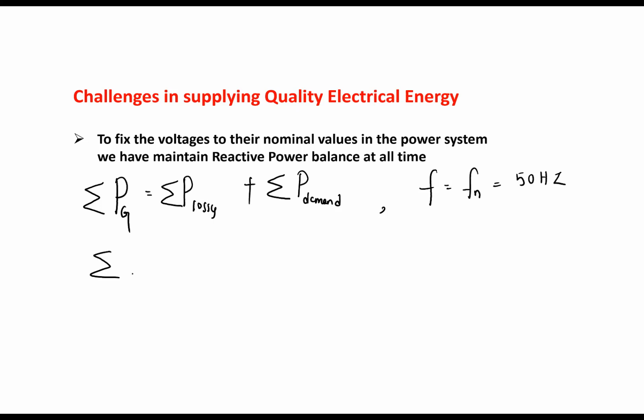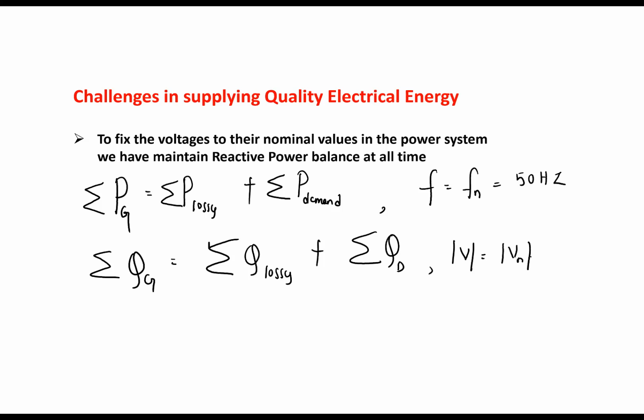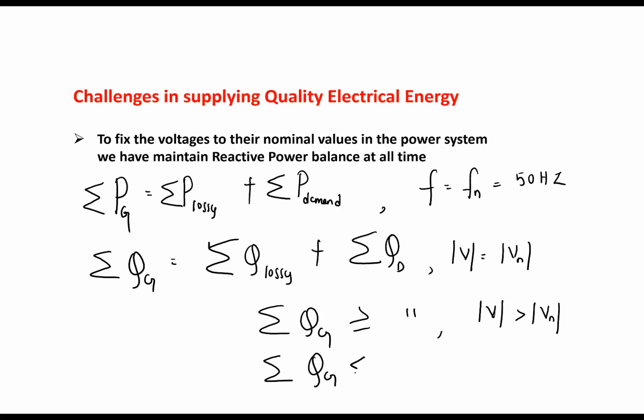Similarly, if the total reactive power generation equals the total reactive power losses in the system plus the total reactive power demanded by the system, then your voltage magnitude at every point will be equal to its nominal voltage. The main point is real power balance will fix the frequency, reactive power balance will fix the voltage magnitude to its nominal voltage. If Qg is greater than the above quantities, your voltage will overshoot and you will get an over voltage problem. If there is lesser generation of reactive power than required, your voltage magnitude will be less than nominal, and a low voltage problem will come.